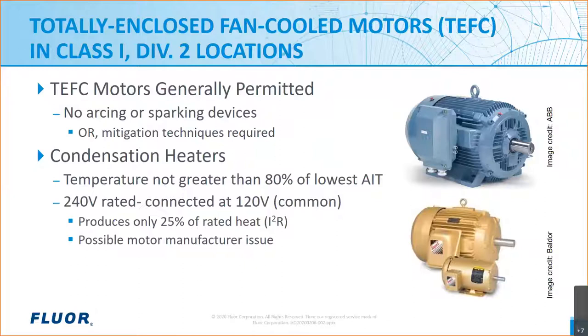As shown in this slide, we also mentioned the common practice of specifying space heaters rated for 240 volts and yet supplying them at 120 volts. This may add to the lifespan of the heater, but does result in a couple of possible issues. First, only 25% of the wattage at the rated voltage is produced, reducing the amount of heat, and therefore it may not be possible to keep condensation from forming. Second, motor manufacturers may not be willing to provide 240V-rated heaters for a 120V application because of concerns they may be inadvertently connected to 240 volts, resulting in a temperature exceeding 80% of the AIT.